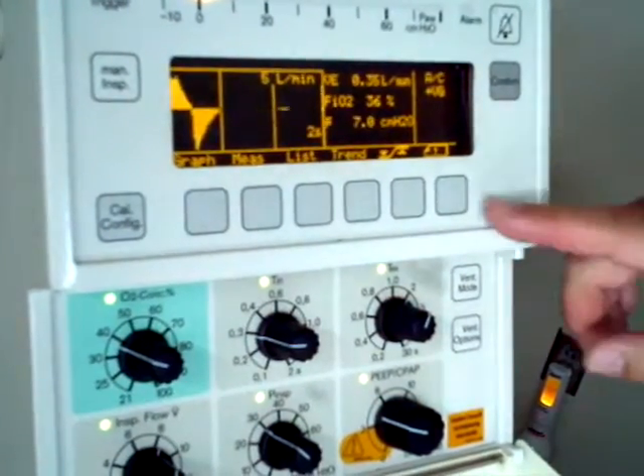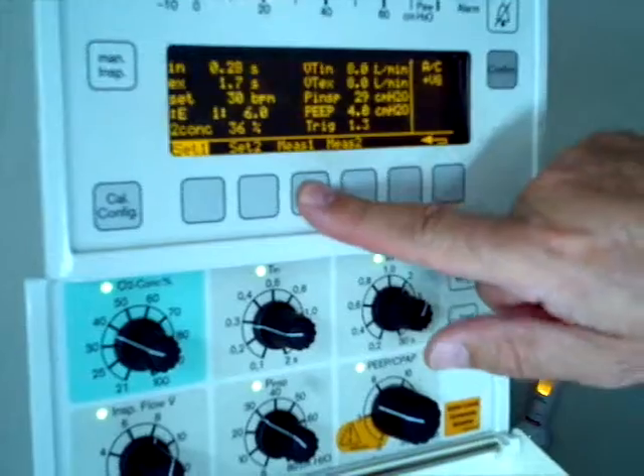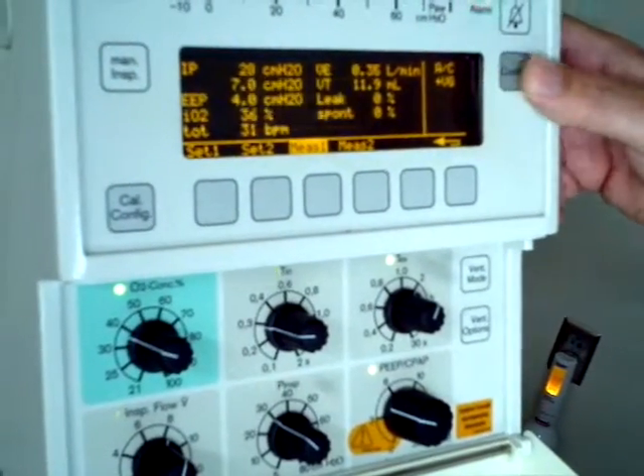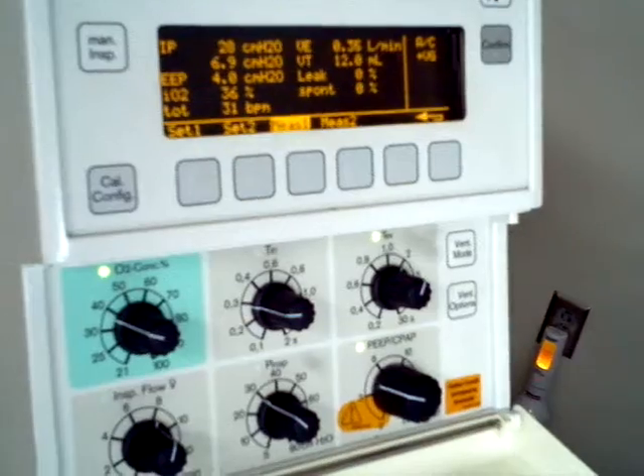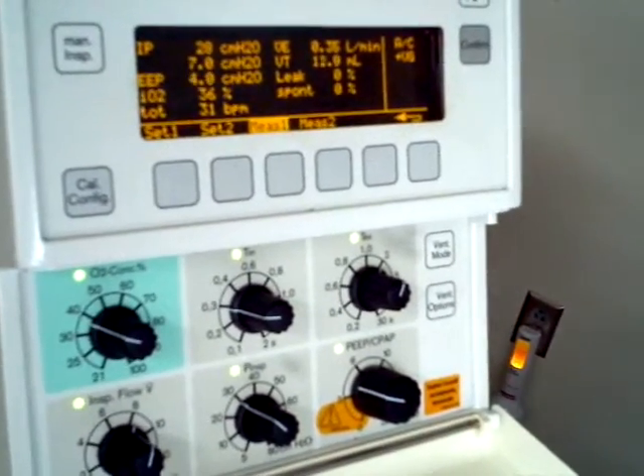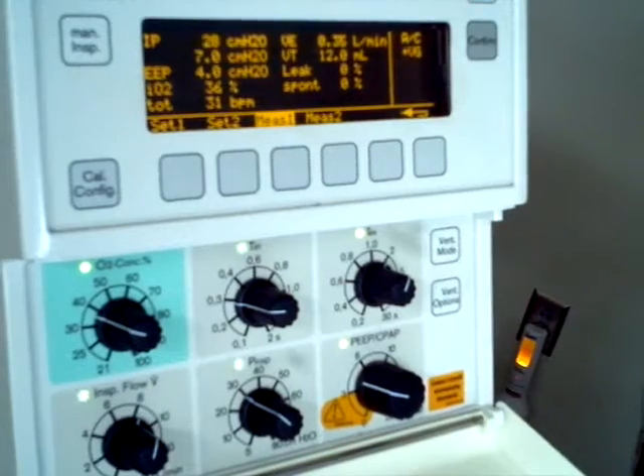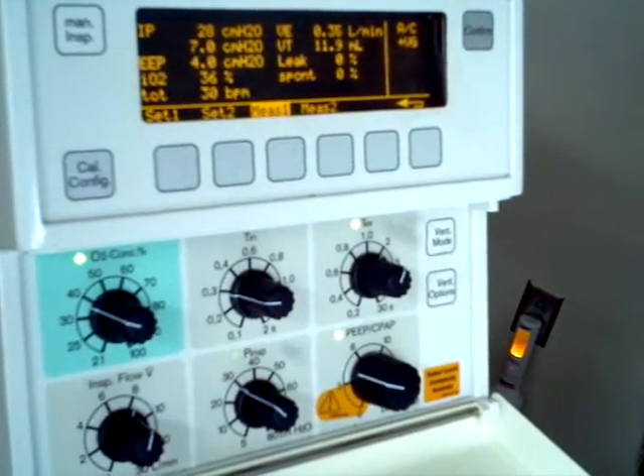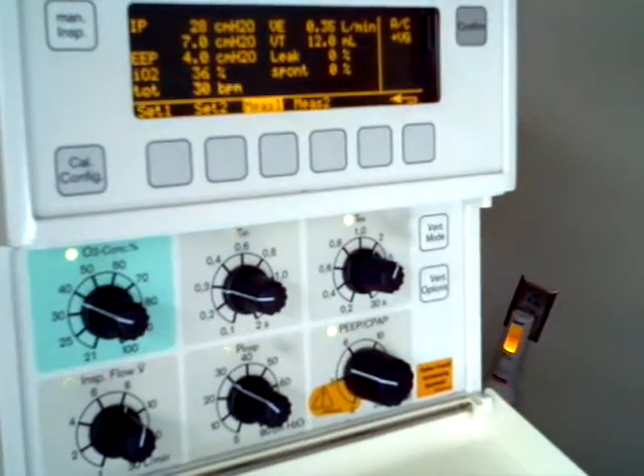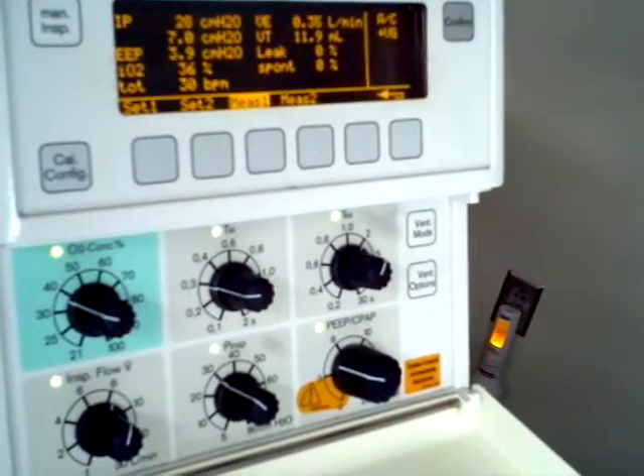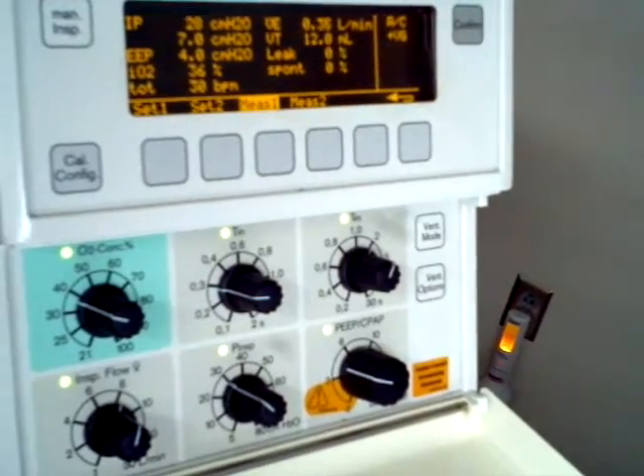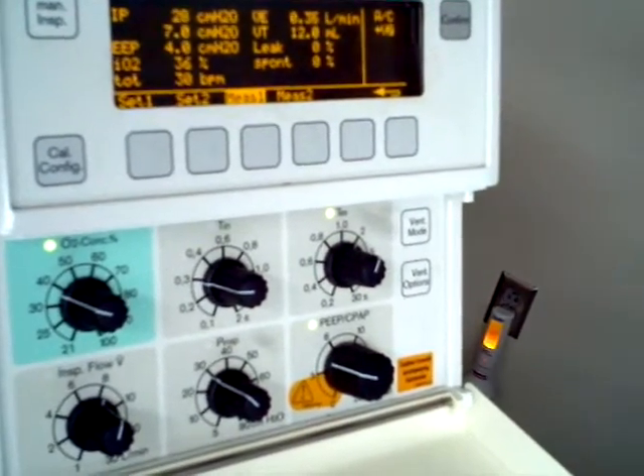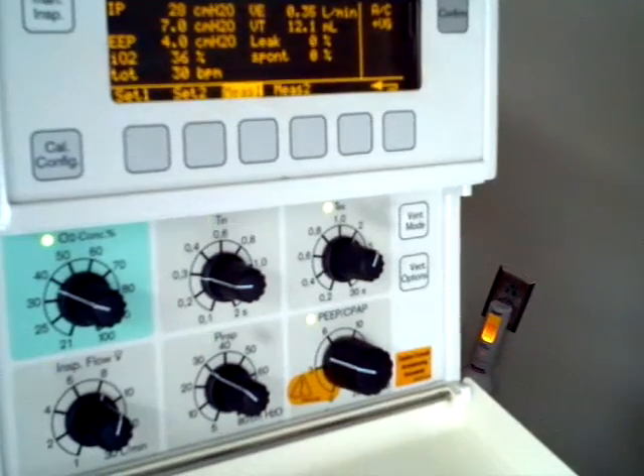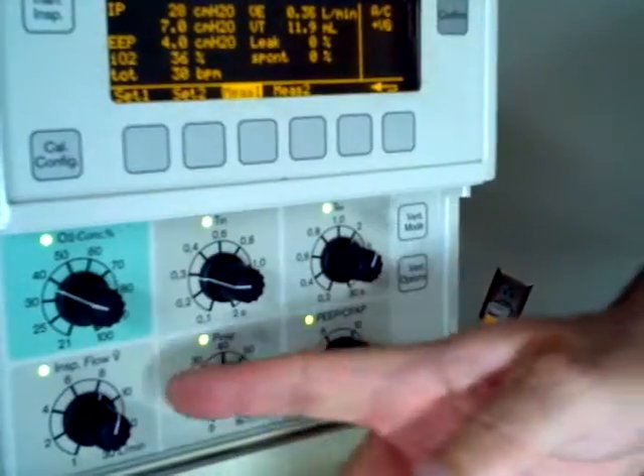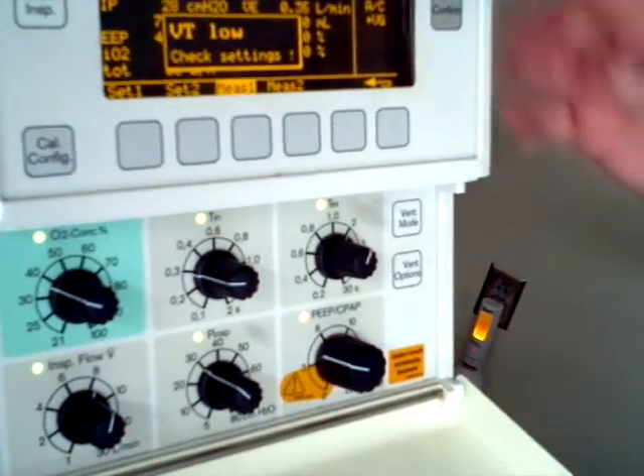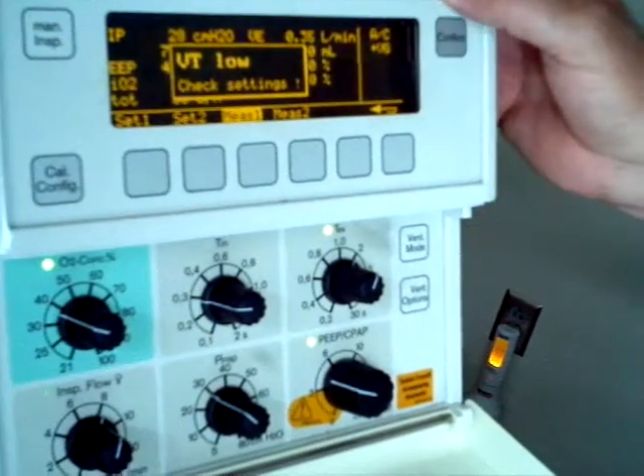Okay. It's always a good idea to double check your measured tidal volume. Ah, you spoiled it. Well, not really. What's my tidal volume reading? Huh. Lo and behold, it's at 12. And my ventilator is telling me, yeah, basically the volume guarantee is not guaranteed right now. And it gives you a little help in that it shows the 3 knobs you need to address to get it. It says tidal volume low, check settings.